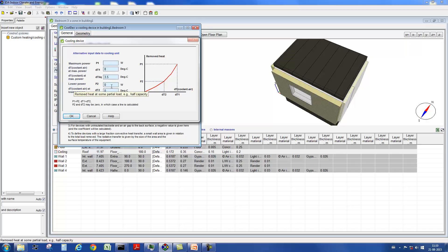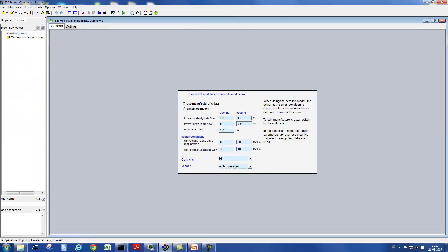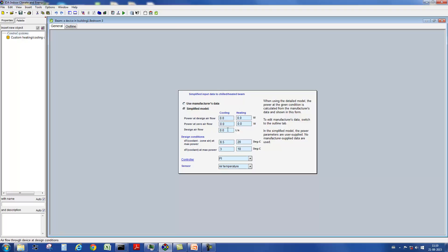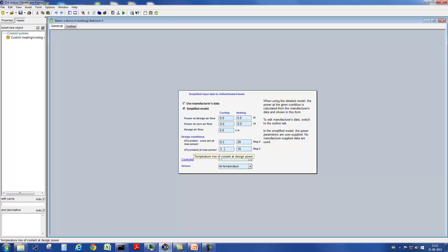Also available are chilled beams. The user defines the cooling power under design airflow and when no airflow occurs, as well as the design airflow itself. Also required is again the temperature difference between the air and the water, and the delta T of the water itself under design conditions, and again the controller type.